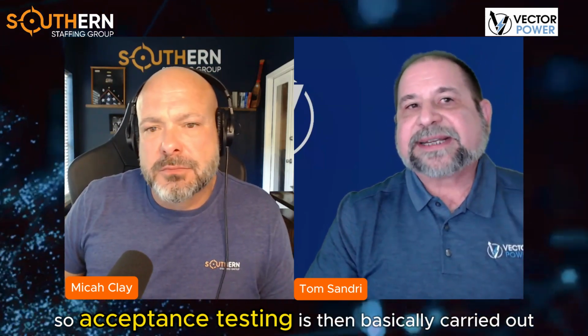So acceptance testing is basically carried out after the terminations and splices are in place, but before energization. Really at this stage, we can say we know the cable's good, I did that during the installation. So what I'm focusing on now is the quality of the splices, the terminations, and the workmanship in putting them all together. And then maintenance testing is anytime after you've energized, whether it's for preventative maintenance, anytime that you bring it back down to retest after it's been energized, technically that would fall into the category of a maintenance level test.